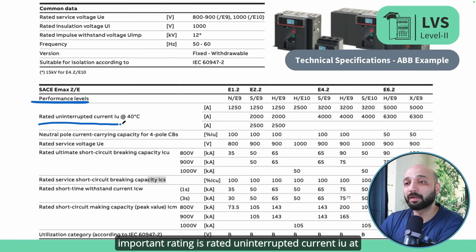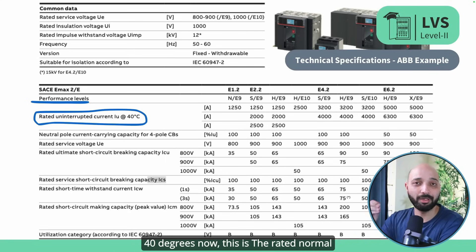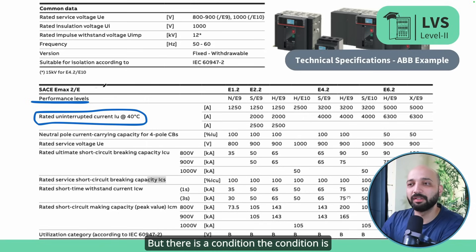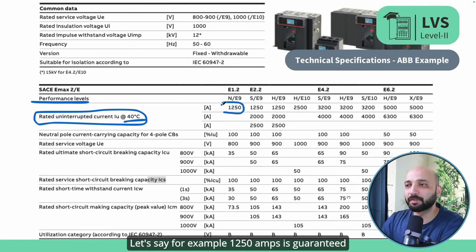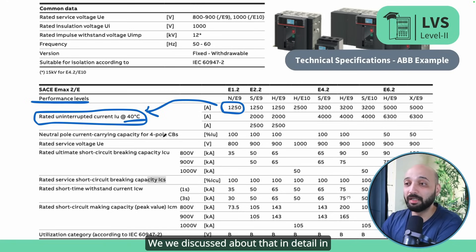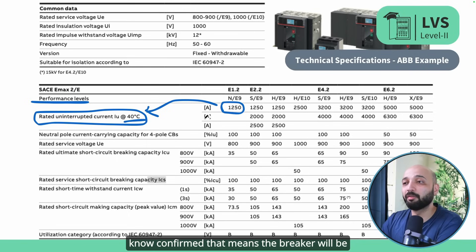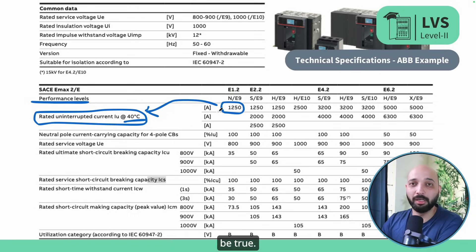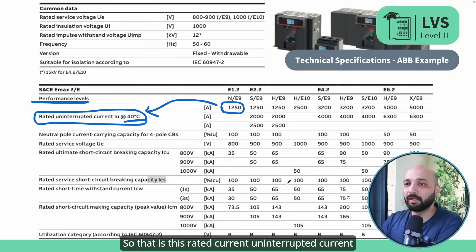The next important parameter is rated uninterrupted current, Iu, at 40 degrees. This is the rated normal current the breaker can carry continuously without any problem, but only at the rated ambient temperature of 40°C. For example, 1250 amps is guaranteed only at 40°C ambient. If your site temperature exceeds that, you need to consider a derating factor. Beyond 40°C, the breaker may not be able to carry the rated current without overheating, so derating must be applied.